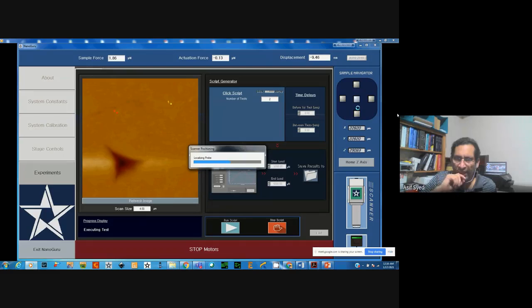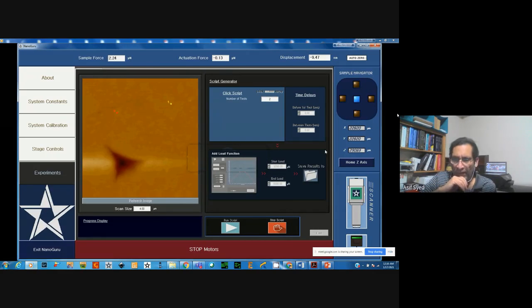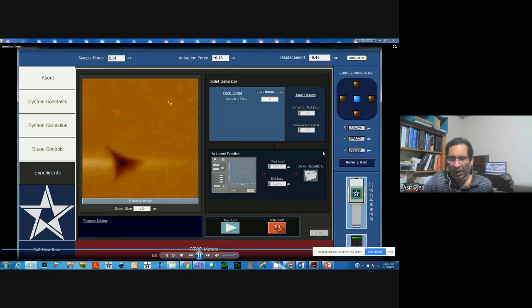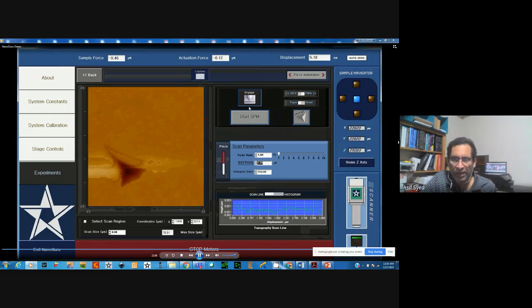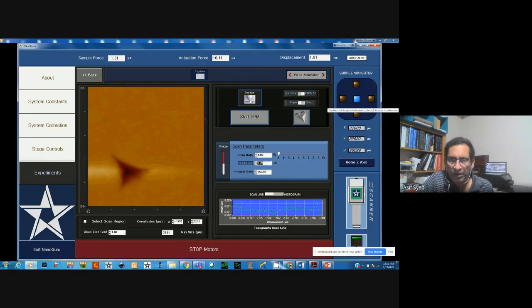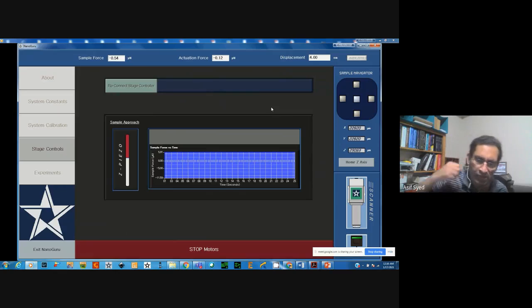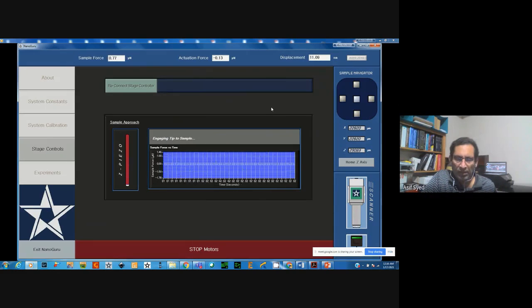It will wait a few seconds for the scanner to position again, and then once it is done, it will say the experiments are done. Then you can go back to the SPM imaging to see whether the indents are done in the place where they were supposed to be. Now it's done. You exit from here, and it will take you to the SPM image window. Then you engage again to image the surface. So the piezo is stepping towards the sample. It will take only 20 seconds now because we already know the surface. Within 20, 21 seconds, it will find the surface again.